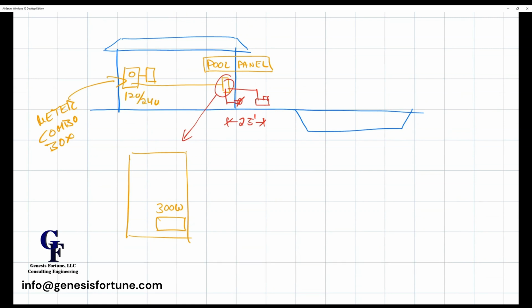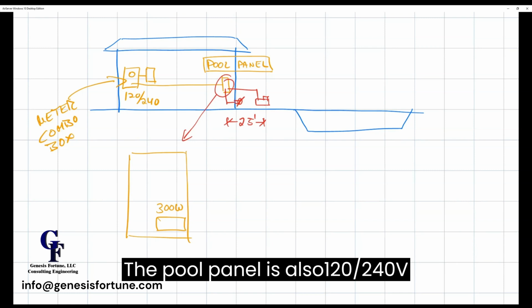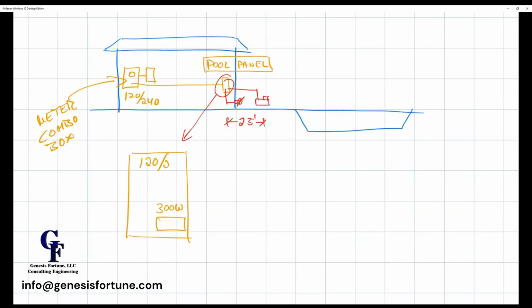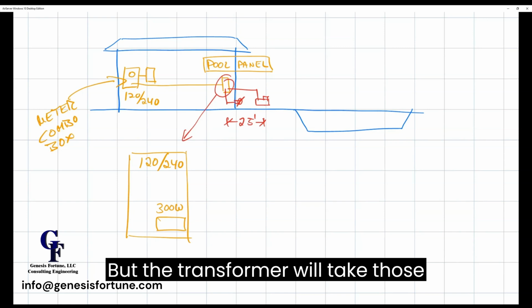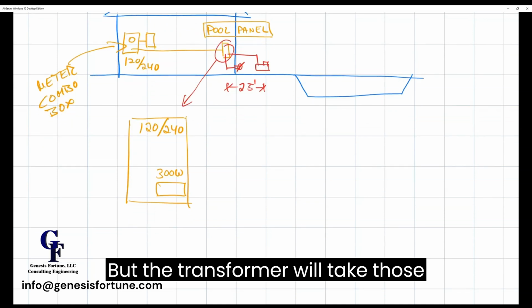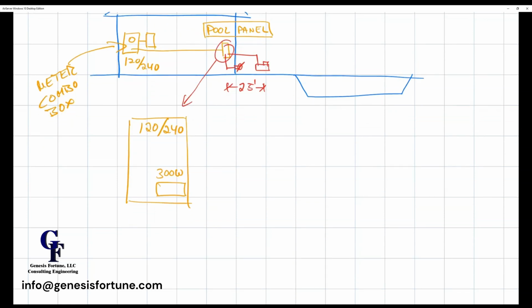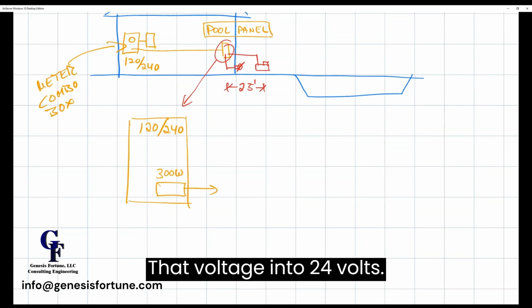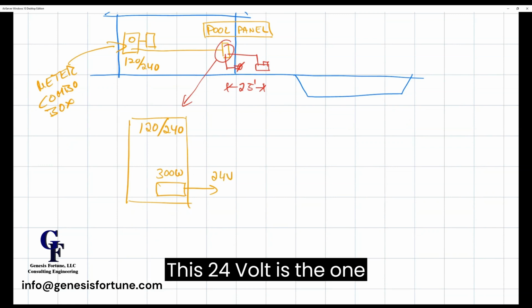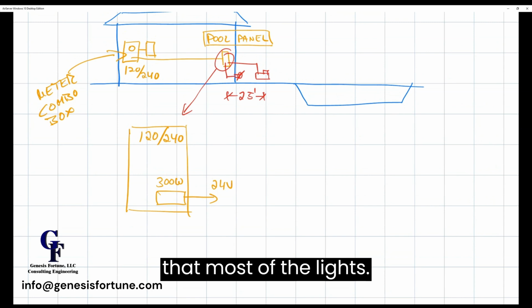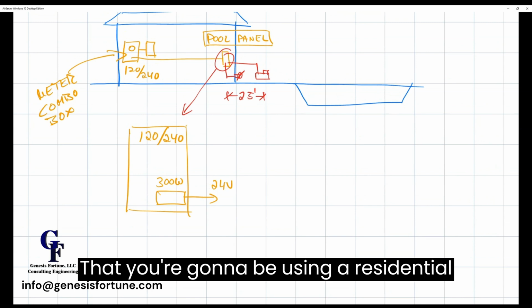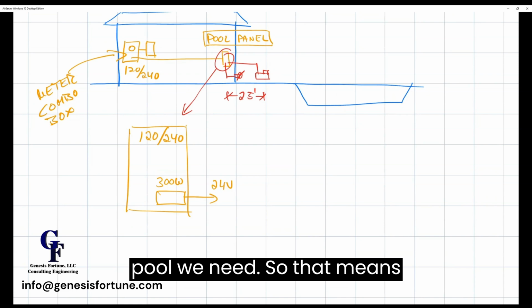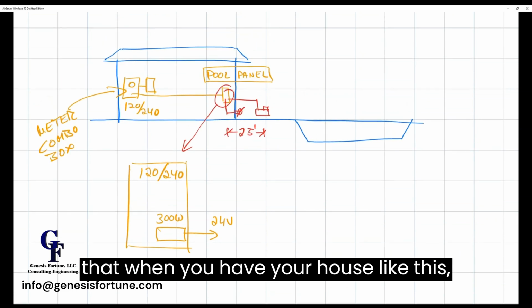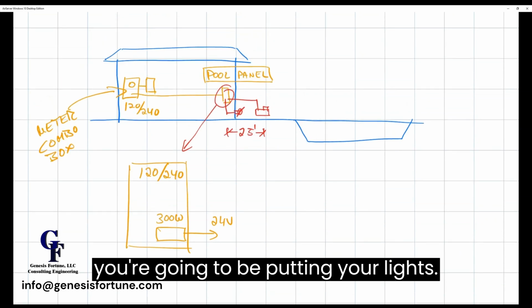What this transformer does is that when the voltage from the meter combo is 120/240, the pool panel is also 120/240. But the transformer will take the 120 volts and transform that voltage into 24 volts. This 24 volts is what most of the lights you're going to be using in a residential pool will need.